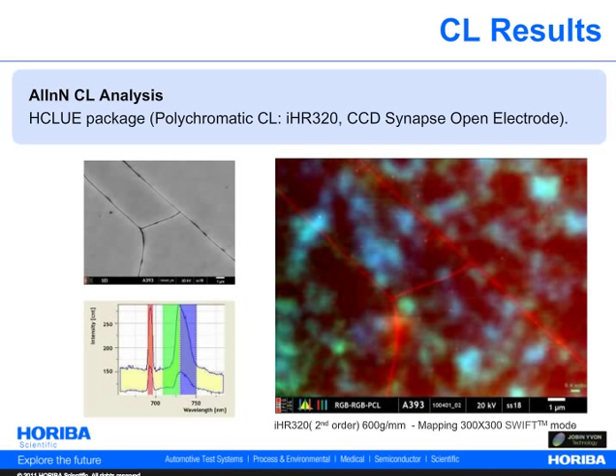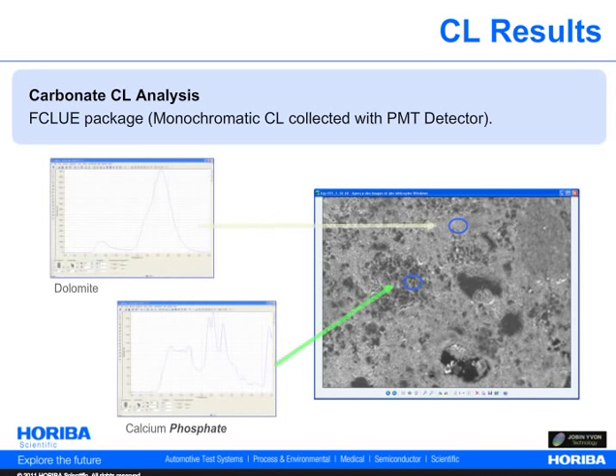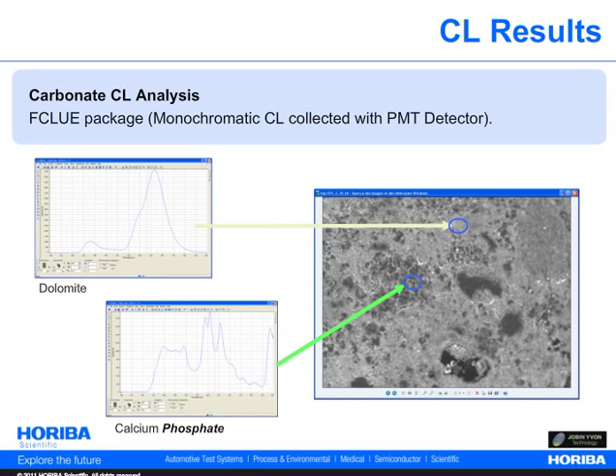The second example deals with the characterization of a two-layer stack sample comprising an aluminum indium nitride layer deposited on a gallium nitride layer on a sapphire substrate. The mapping at the wavelength of chromium at 694 nm clearly shows the cracks. In this last example, we illustrate the software capability to select an area on the SEM image to perform a cathodoluminescence measurement, showing the identification of different types of carbonate in the sample under analysis.